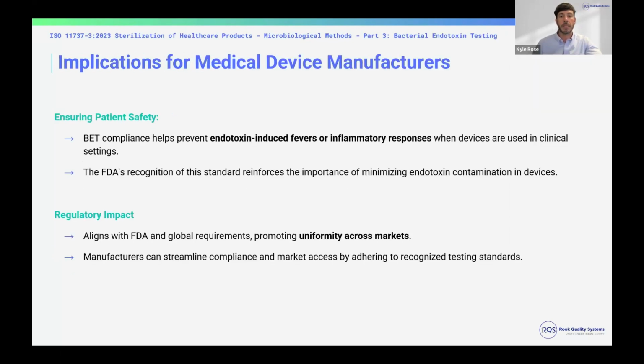Implications for medical device manufacturers and companies. The bacterial endotoxin testing has been around for a while, but this is more aligning with the updated standard that came out in 2023. This testing helps prevent endotoxin-induced fevers or inflammatory responses when devices that potentially have endotoxins are used. This standard reinforces the importance of this testing and minimizing endotoxin contamination in devices.